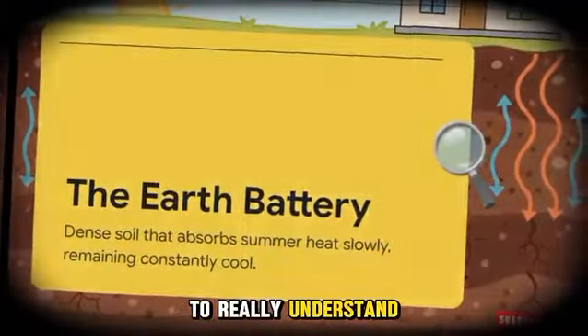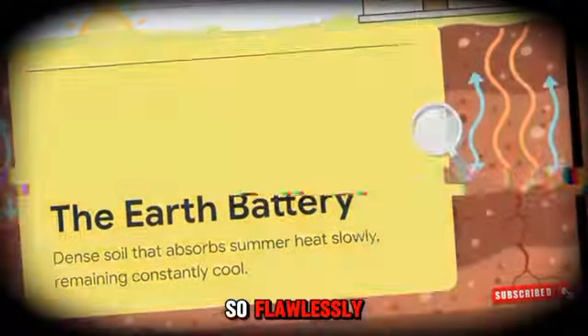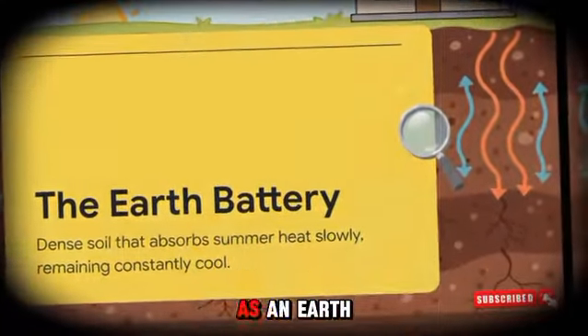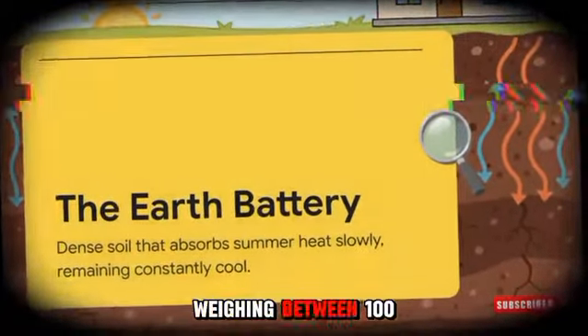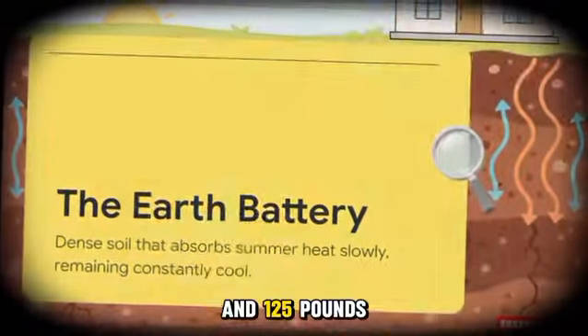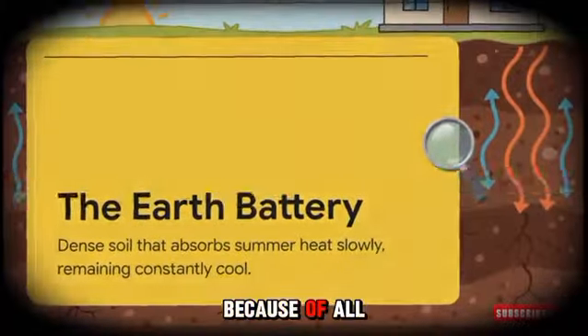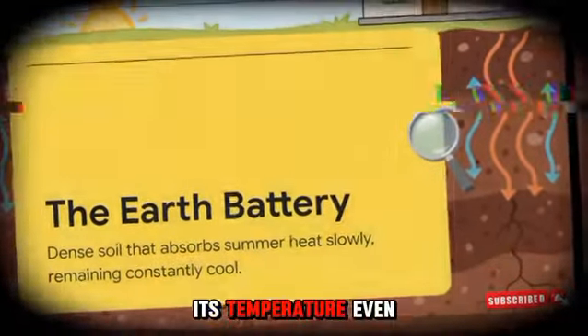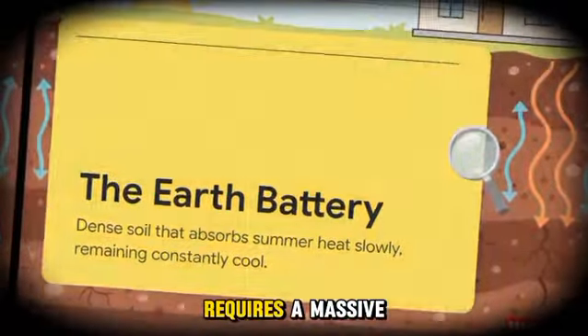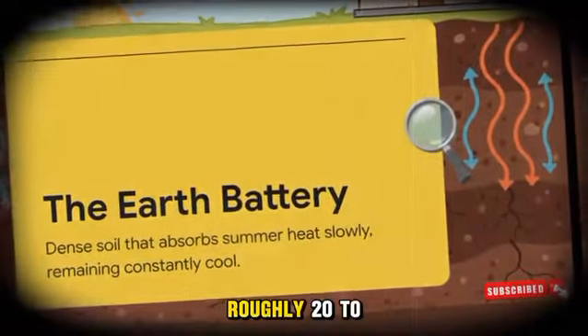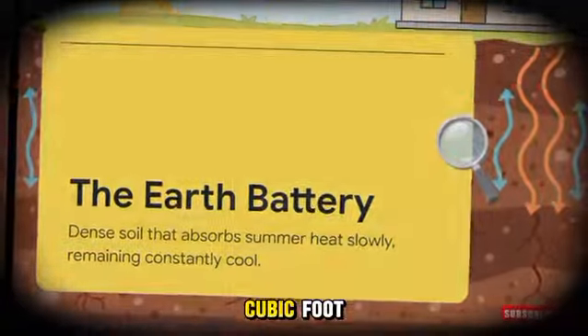To really understand why this works so flawlessly, we have to look at what the dirt is actually doing. Think of it as an earth battery. Soil is incredibly dense, weighing between 100 and 125 pounds per cubic foot. Because of all that mass, moving its temperature even 1 single degree requires a massive amount of energy, roughly 20 to 30 BTUs per cubic foot.